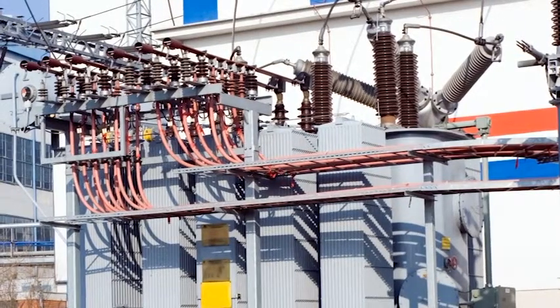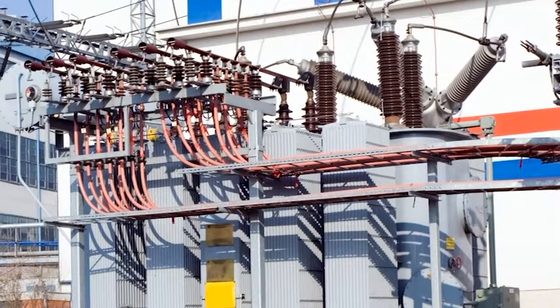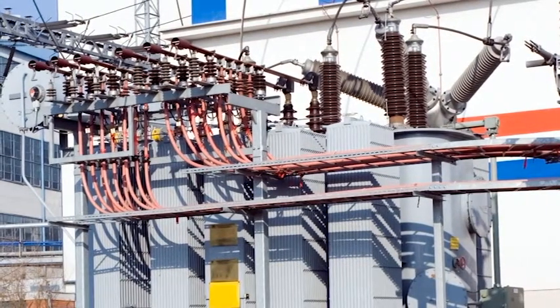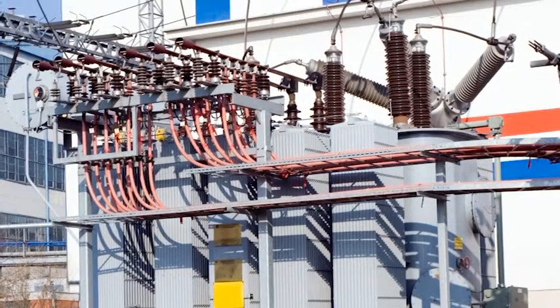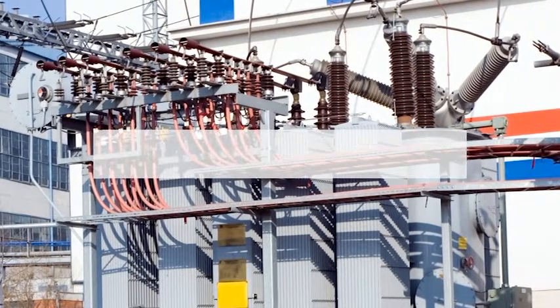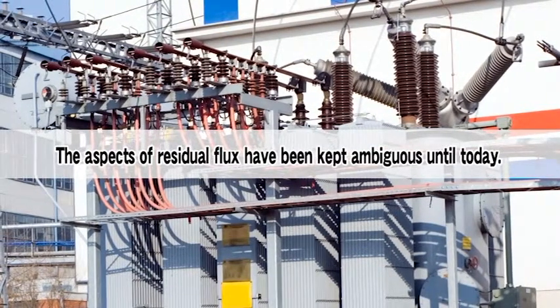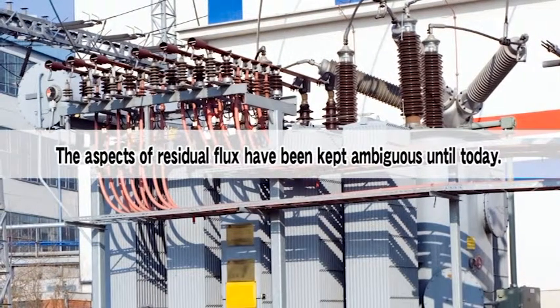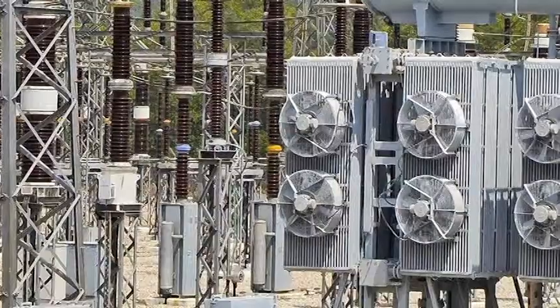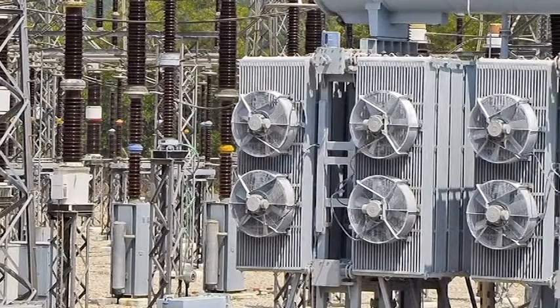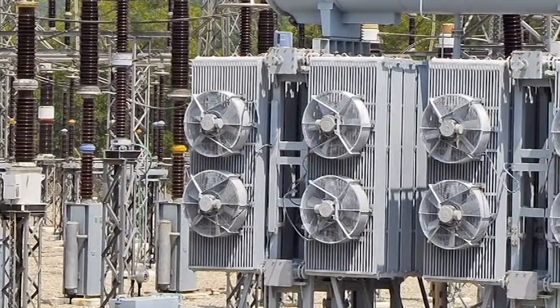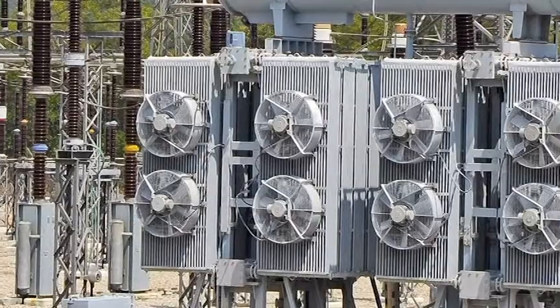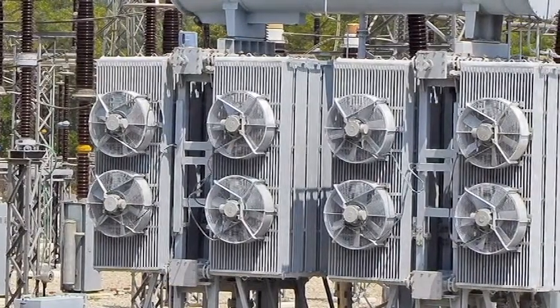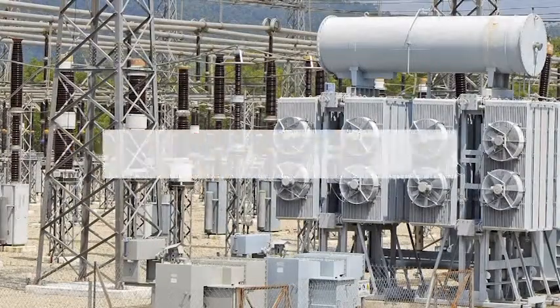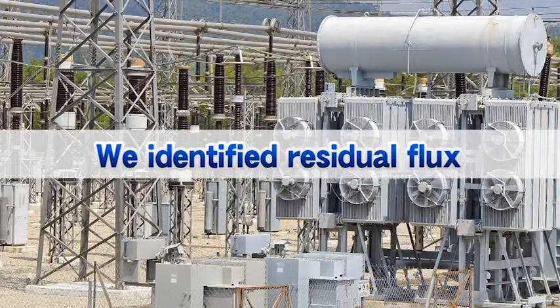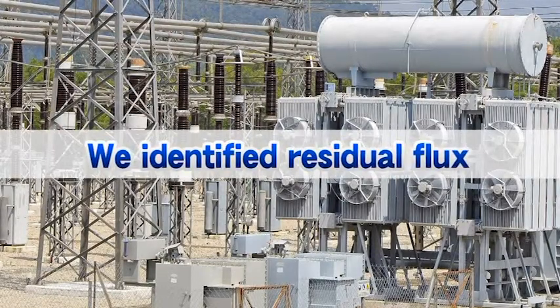Inrush current is generated by the residual fluxes in the transformer core, which are released when the transformer is shut down by tripping the circuit breaker. Until now, this aspect of residual fluxes was kept ambiguous. This is because there is no way to directly measure the fluxes, and it is difficult to test for in an actual system. Koudensha has succeeded in accurately assessing the nature of residual fluxes.